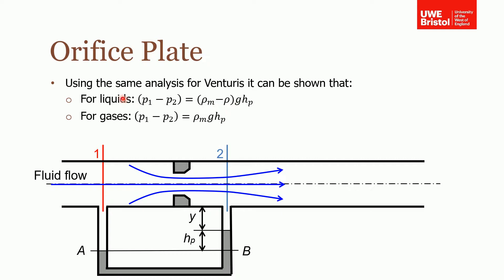Using the same analysis for the Venturi we can show that for liquids the change in pressure is equal to the density of the manometer minus density of the fluid in your pipe times G times HP. And for gases that term can be neglected because it's small compared to the density of the fluid in the manometer.